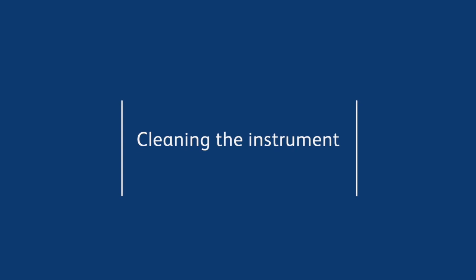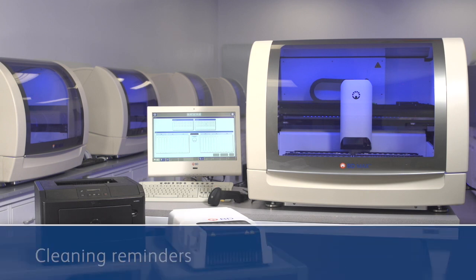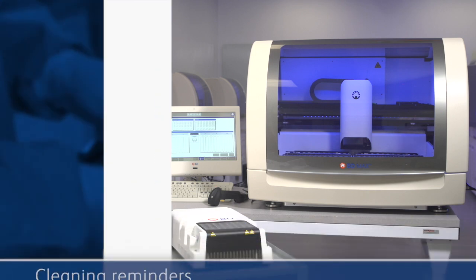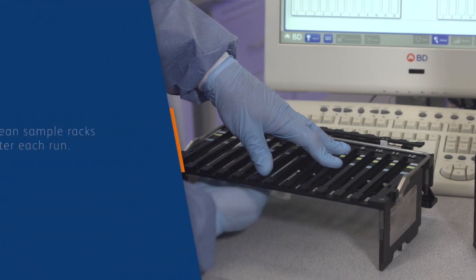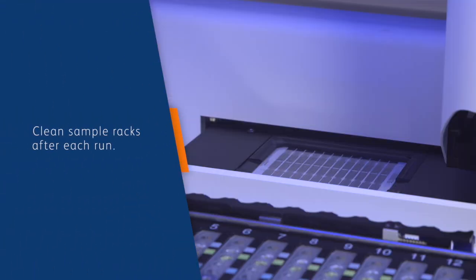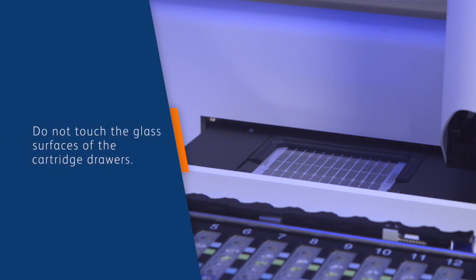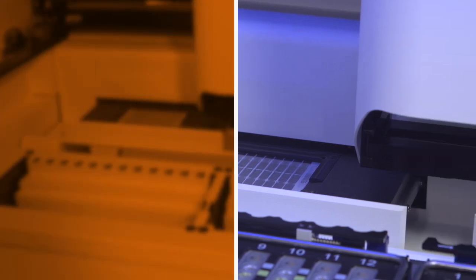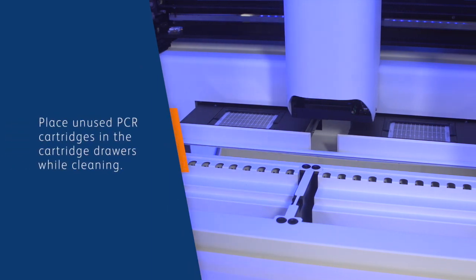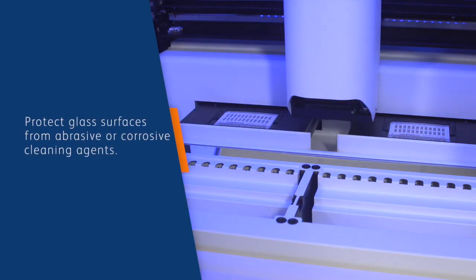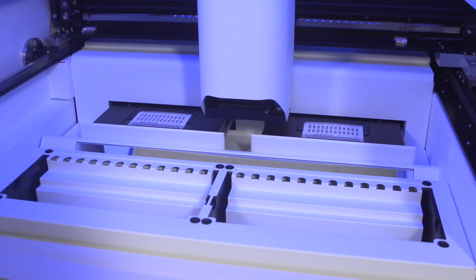To keep the BD Max system operating at peak efficiency and ensure a long life, you should observe a strict daily and weekly cleaning and maintenance regimen, remembering that sample racks should be cleaned between each run. Be careful not to touch the glass surfaces of the cartridge drawers. If any foreign objects, dust, or dirt are discovered on these surfaces, review the user's manual for proper cleaning procedures. It's also recommended that you place unused PCR cartridges in the cartridge drawers when cleaning. Finally, take care to protect the glass surfaces from any accidental splattering of abrasive or corrosive cleaning agents.